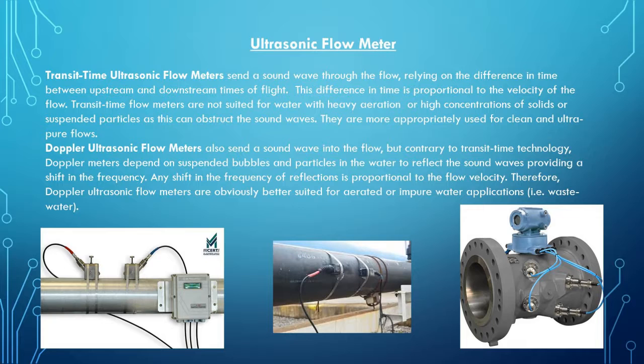Doppler ultrasonic flow meters work due to the Doppler effect. A transducer emits an ultrasonic beam into the flow. Air bubbles or solids in the liquid shift the frequency of the beam before being received by the second transducer. These shifts are proportional to the velocity of the liquid.